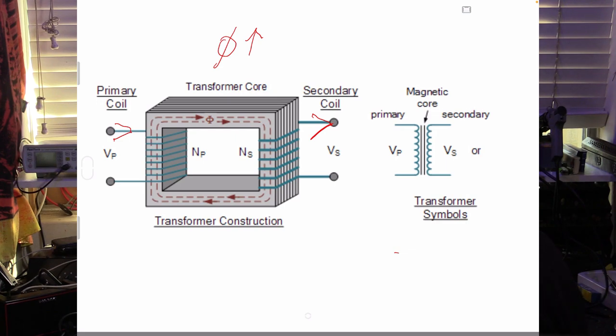At this point, negative things start to happen in the transformer. The secondary voltage will no longer be sinusoidal. When it's no longer sinusoidal, that means the transformer is now creating harmonics above the mains 50 or 60 hertz. These higher frequencies are causing overheating because the transformer was just not designed to handle more than mains frequencies, low frequencies. As the transformer gets hotter, it loses efficiency, it loses power.